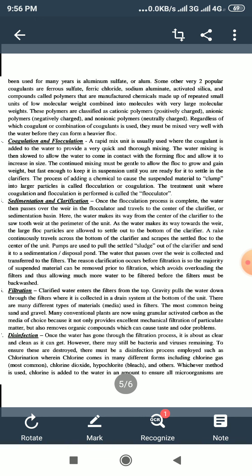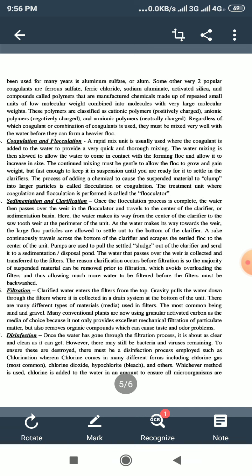Coagulation and flocculation. A rapid mix unit is usually used where the coagulant is added to the water to provide very quick and thorough mixing. The water mixing is then slowed to allow the water to come in contact with the forming floc and allow it to increase in size. The continued mixing must be gentle to allow the floc to grow and gain weight, but fast enough to keep it in suspension until you are ready for it to settle in the clarifiers.